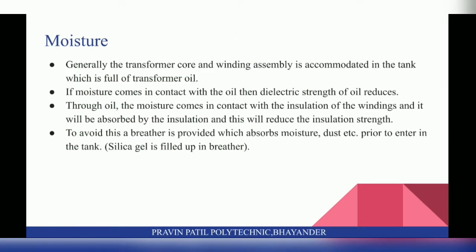The first factor is Moisture. Generally the transformer core and winding assembly is accommodated in the tank which is full of transformer oil. If moisture comes in contact with the oil then the dielectric strength of the oil reduces. Through the oil, moisture comes in contact with the insulation of the windings and it will be absorbed by the insulation, reducing the insulation strength. To avoid this, a breather is provided which absorbs moisture, dust etc. prior to entering the tank.